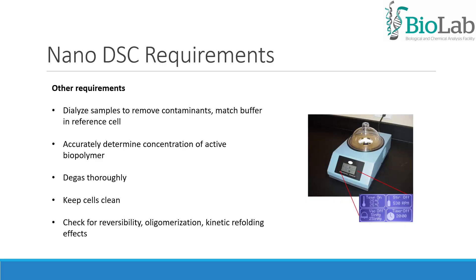For a successful experiment, you should dialyze samples to remove contaminants, match the buffer in the reference cell, accurately determine the concentration of active biopolymer, degas thoroughly, keep cells clean and check for reversibility, oligomerization and kinetic refolding effects.